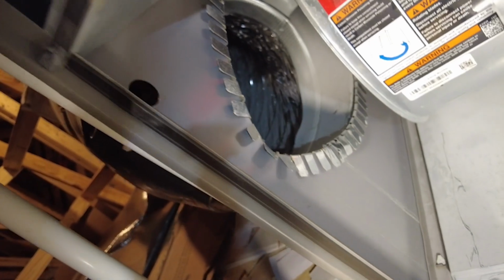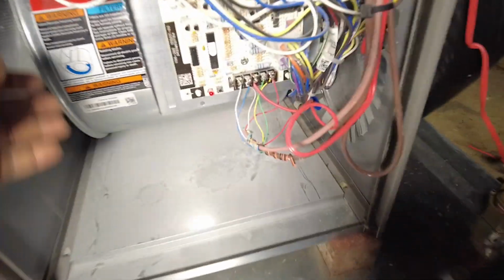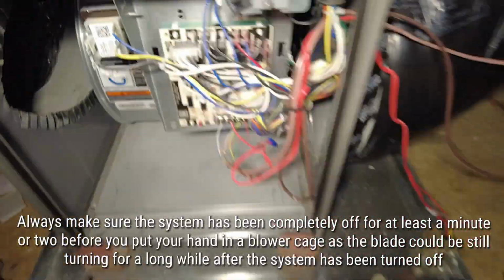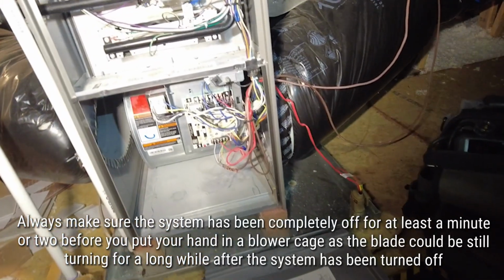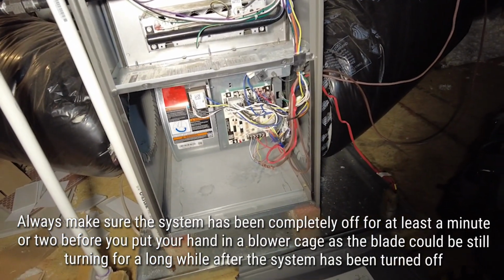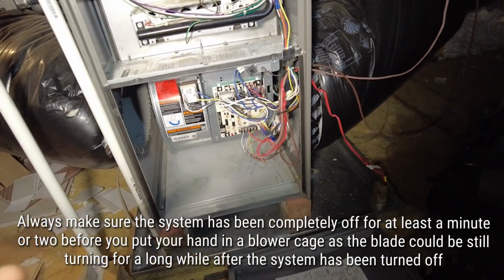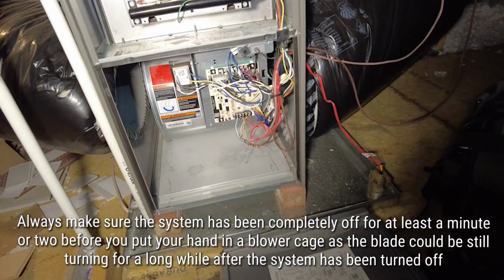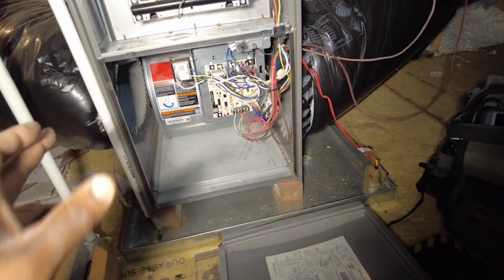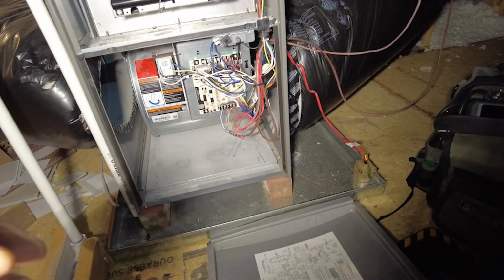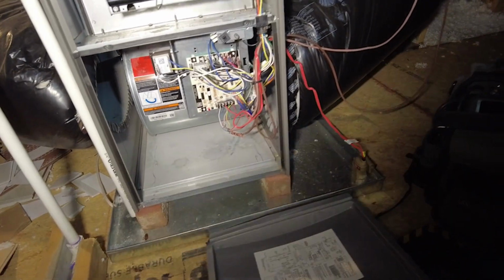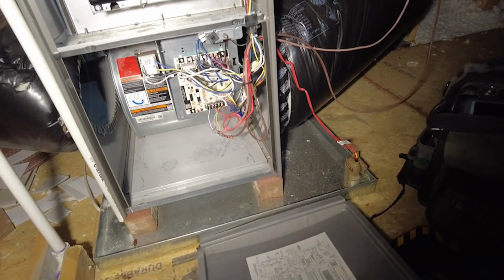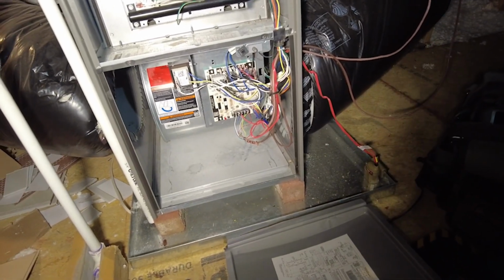Check out that diamond-shaped duct they put in. That's pretty interesting, huh? Like I said, make sure you visually check and see it. But you can also feel. See how I'm feeling in there? Feeling the blade. That feels crispy. It feels clean. If you feel grit and stuff like that pulling up off with your fingernails, then that's shot. You probably want to let them know, hey, the blower needs to be clean. Give them the price on that. Because it's pretty important. That blower wheel can have the smallest amount of dirt on it, and that will affect the airflow significantly, just based off of not even having much dirt on those fins there.